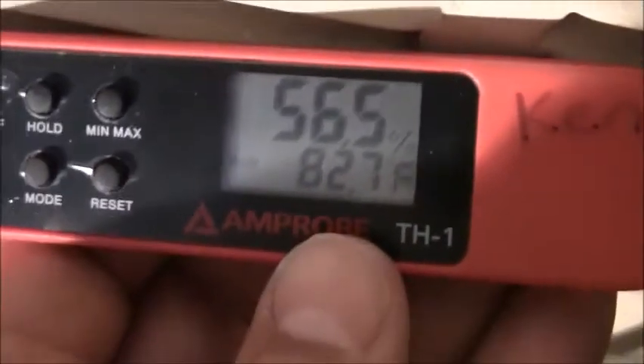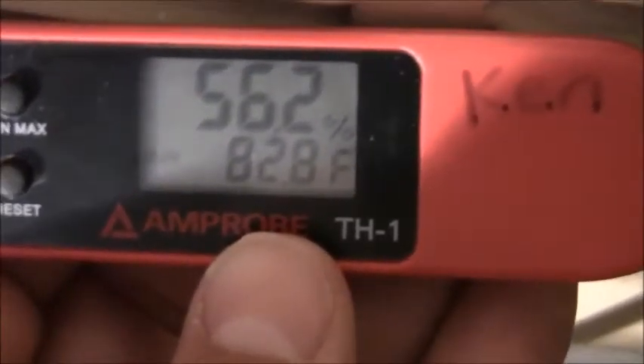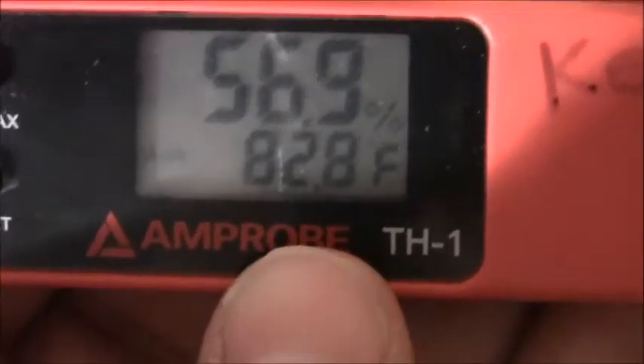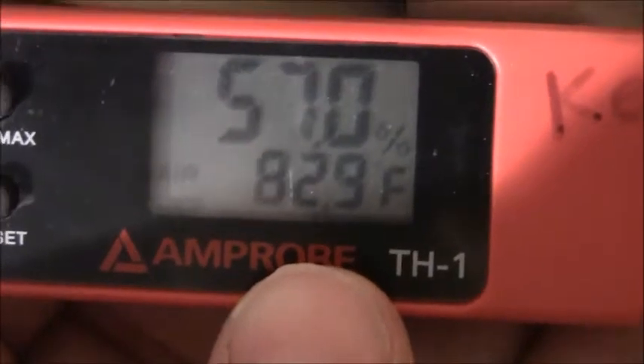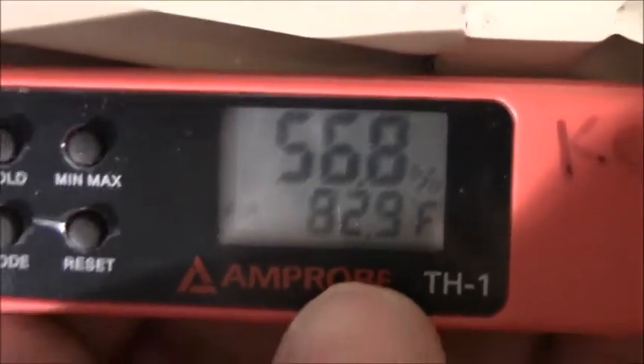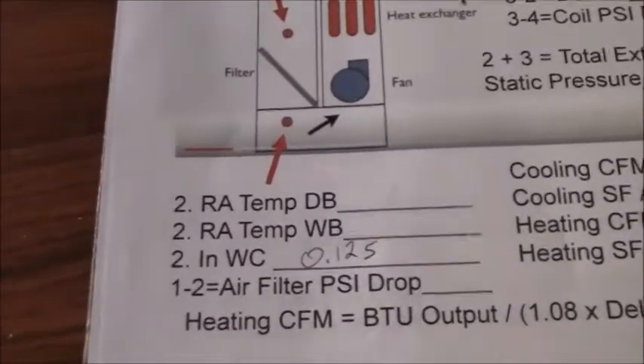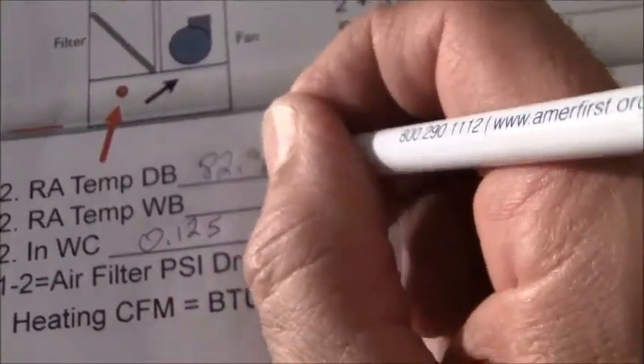Now, as long as we're here, let's get our return air dry bulb and wet bulb. I got my thermometer here. Vents are open on it, and let's go ahead and see what that is. Okay, so the dry bulb temperature is showing 82.7. Oh, come on. 82.7. 82.9. Okay, we'll call it 82.9. So we're going to put down here the dry bulb temperature is 82.9.